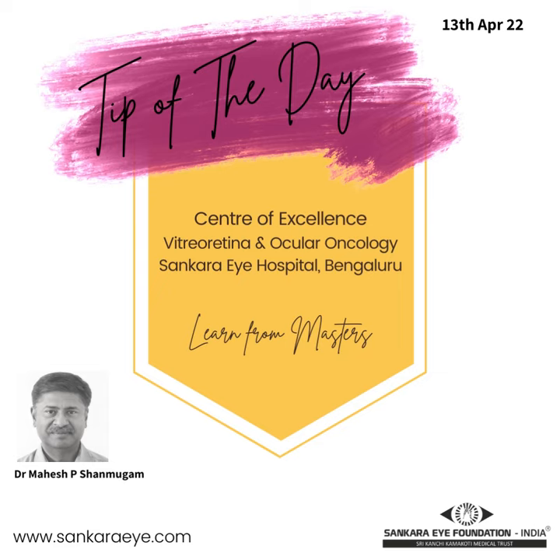In indirect ophthalmoscopy, the observer's pupils are brought together with the use of prisms. The light source, the condensing lens, and the patient's pupil should be in a single axis. When any of these components are not in this axis, a good binocular image will not be seen.